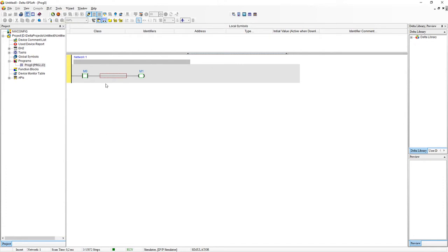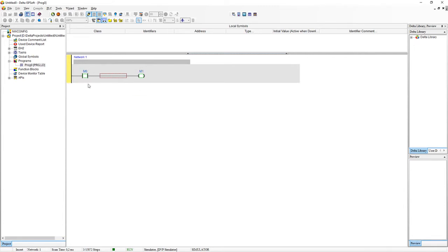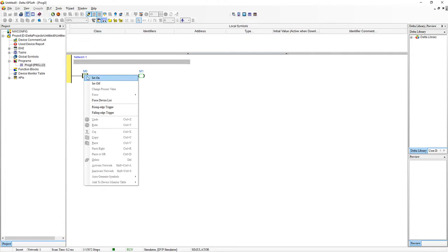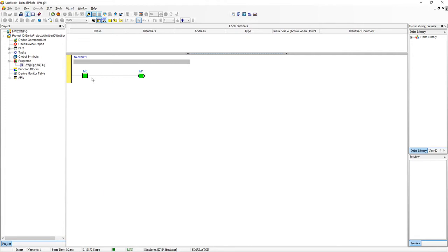If it is not then you'll just have to click on this button to run. And if you want to stop the simulation just click on stop. So now we're in the run mode and just to show you how this actually works. Here we typed OUT M1. That means it is an output. And here we typed LD M0 which means it's an input. And what we can actually do while we're in online mode. You can click on this. Right click and we can say set on. And you'll see that this executes and then this executes and turns M1 on.